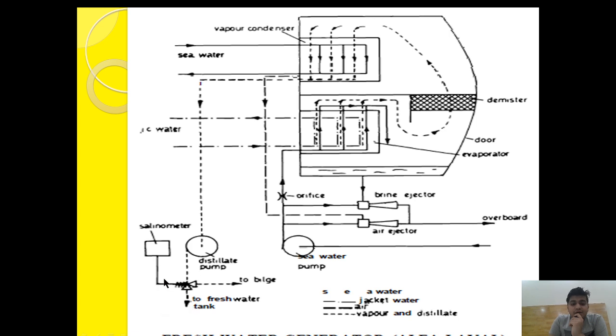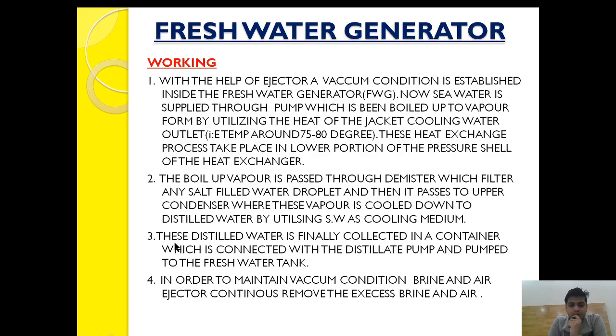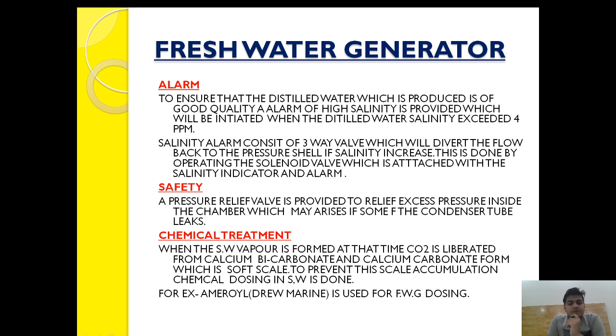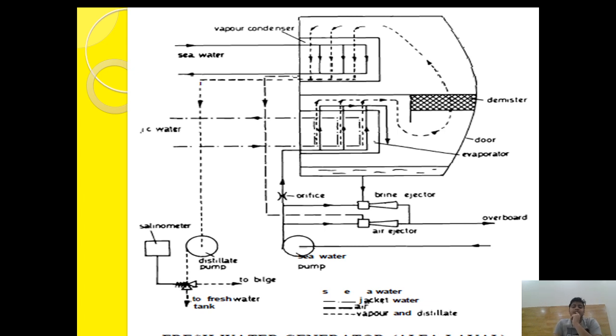The water passing through the distillate pump is sent to the fresh water tank after being monitored through a salinometer. What are the alarms provided in the fresh water generator? A high salinity alarm is provided which will be initiated when the distillate water salinity exceeds 4 ppm. In the shipping industry we normally keep the limit much below that — around 1 ppm. The salinity alarm consists of a three-way valve which will divert the flow back to the pressure shell if salinity increases, operated by a solenoid attached with the salinity indicator and alarm.